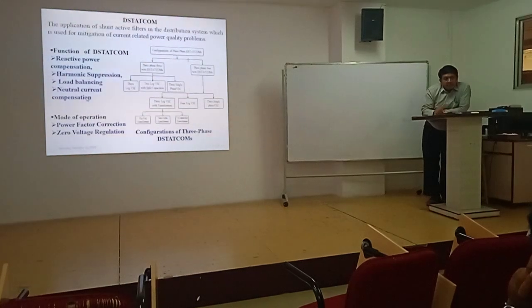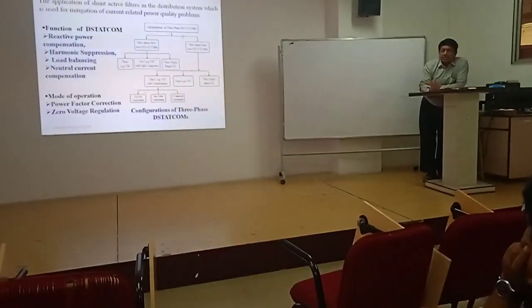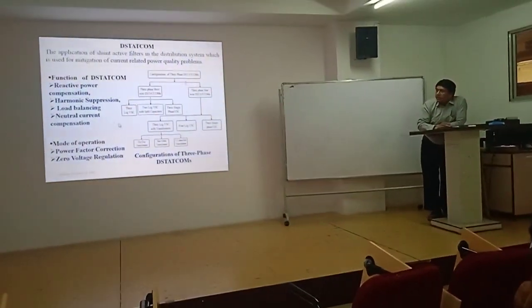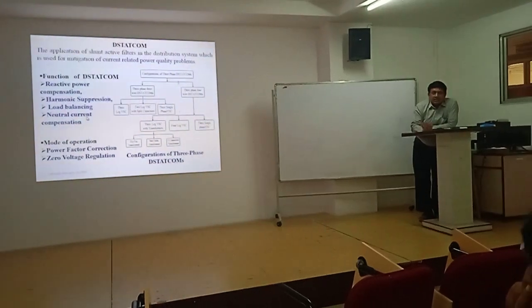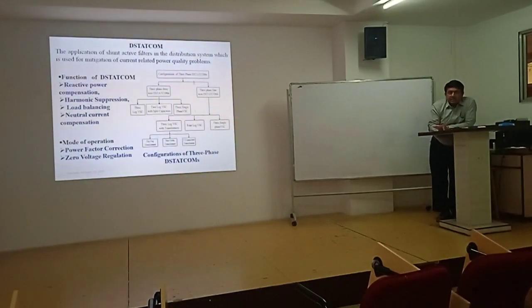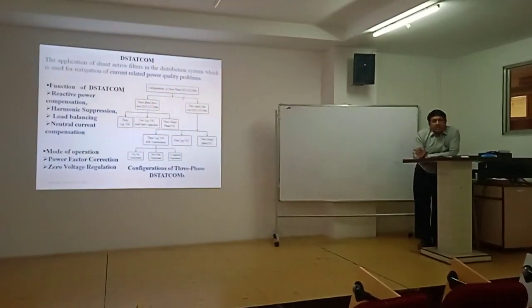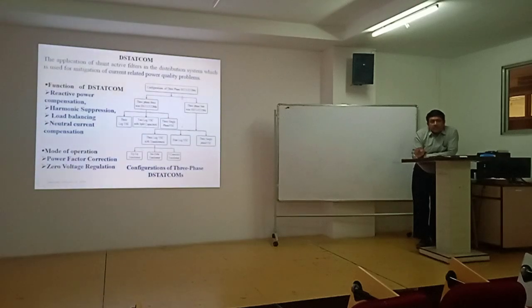By the 4th leg you are going to compensate the harmonic, neutral current frequency. Frequency of neutral current is 150 Hz. The third harmonic value of this one is almost near to load current, if the system is balanced, non-linear. If the system is unbalanced, then the value of neutral current is almost 1.73 times IL. Like that.